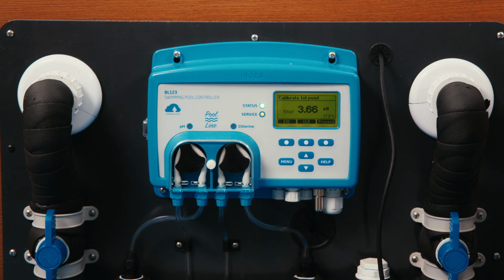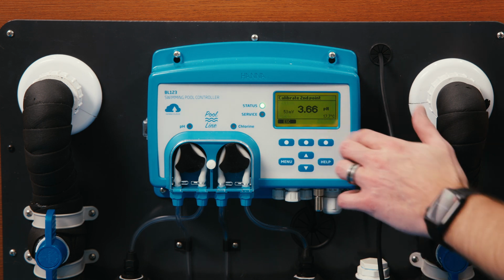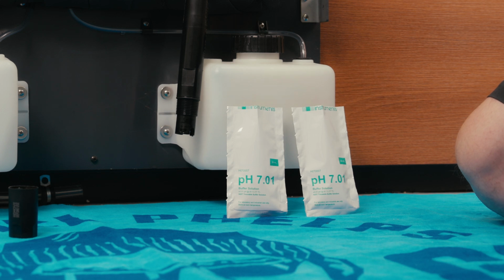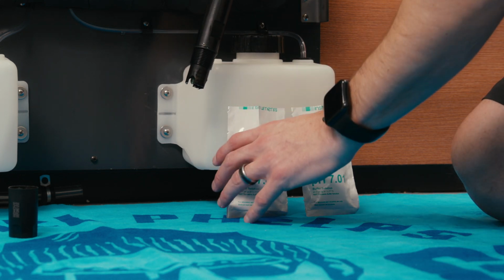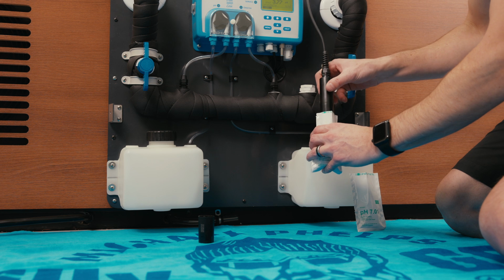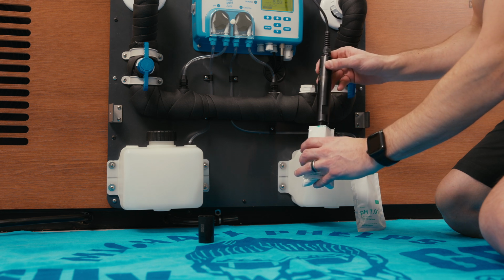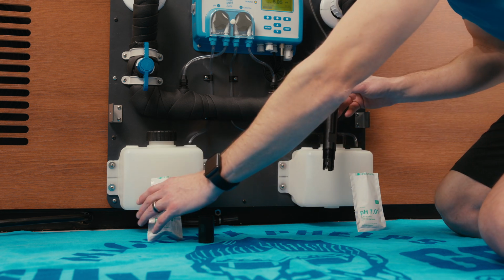Wait for the display to recognize the solution and show that reading is stable. Then confirm to lock the first calibration point. Now we'll repeat the process with the pH 7.01 solution. Open one packet to clean the probe again, gently moving the sensor around in the solution. Then set that packet aside.